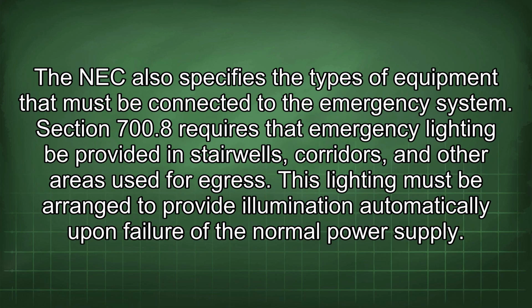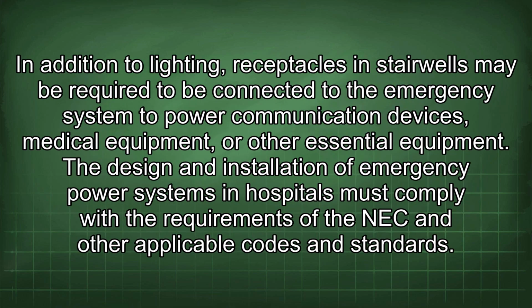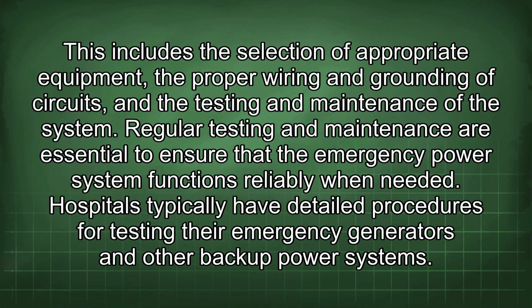The NEC also specifies the types of equipment that must be connected to the emergency system. Section 700.8 requires that emergency lighting be provided in stairwells, corridors, and other areas used for egress. This lighting must be arranged to provide illumination automatically upon failure of the normal power supply. In addition to lighting, receptacles in stairwells may be required to be connected to the emergency system to power communication devices, medical equipment, or other essential equipment. The design and installation of emergency power systems in hospitals must comply with the requirements of the NEC and other applicable codes and standards. This includes the selection of appropriate equipment, the proper wiring and grounding of circuits, and the testing and maintenance of the system.